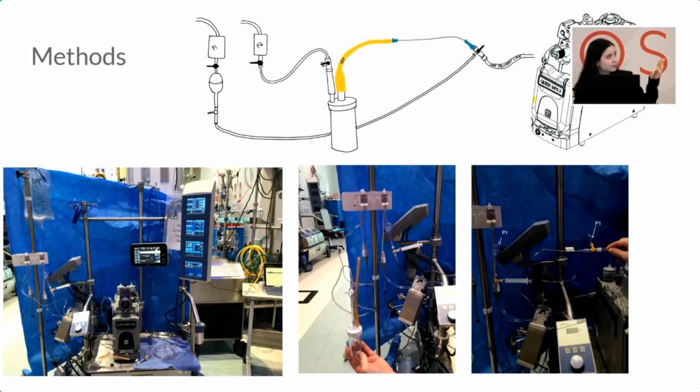The top image might be the easiest to see exactly what's going on, but basically we connected the cardioplegia delivery line to a 3-way stopcock. This stopcock on one end is connected to our P1 pressure, which we use to measure cannula inlet. And then the other side is connected to our Medtronic DLP cannula of choice. The other end of the cannula is then inserted into a cut piece of an 18 French Foley catheter. This then sits on top of our mucus specimen trap. And the other open end of the mucus specimen trap is connected to the second stopcock, which will then measure our P2 pressure, or our post-cannula pressure.